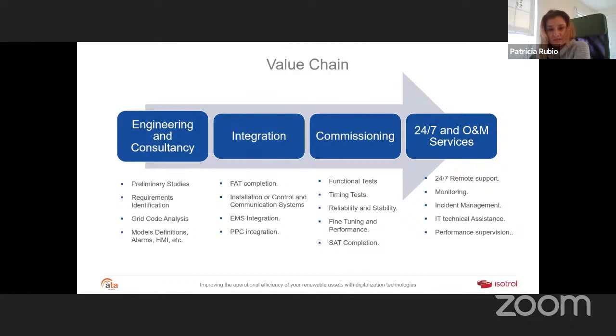During the next phase, the integration phase, we perform what we call the FATs, factory acceptance tests, over the prepared systems that have been built according to the previous design requirements. We then move on to install it and integrate it with the different subsystems and site elements. Following this, we start what we call commissioning. It's a phase that includes the final tests and fine-tuning. We perform functional and timing tests, as well as the typical site acceptance tests. And lastly, once the platforms are shown to be compliant and are accepted by the client, we establish an agreement for the long-term support and services to ensure the maximum stability and perform the adequate updates.